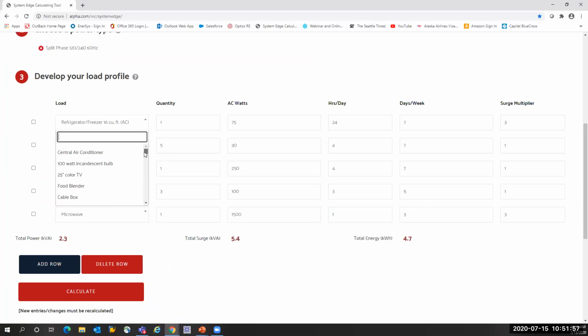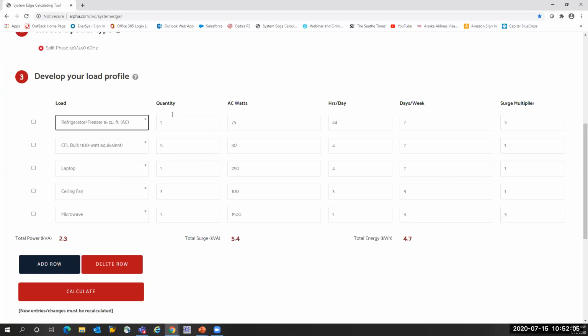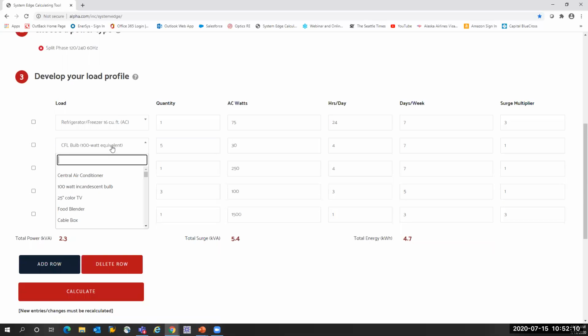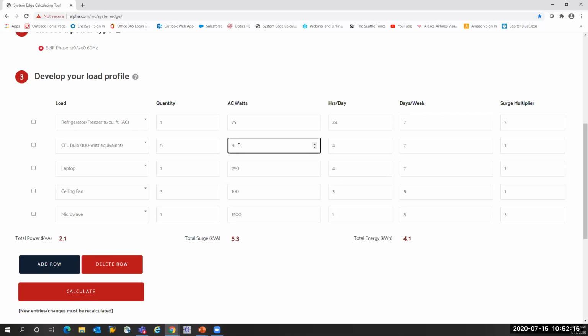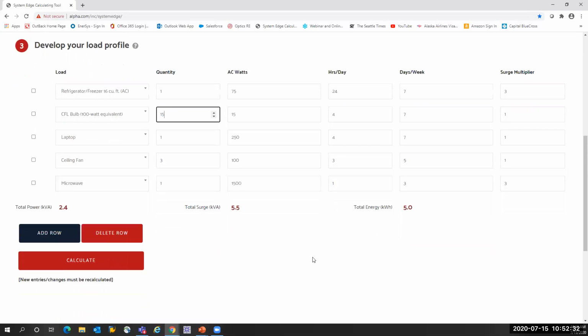from this drop-down menu, you have all these different loads you can choose from. And even if you have one that doesn't match — say, I don't use CFL bulbs anymore, I'm using LEDs that only use 15 watts — you can put that in there, but I've got 15 of them. So you can change the quantities, power, hours per day, days per week. This gives you a much more accurate idea of the customer's load profile, because that's what you're sizing storage to.